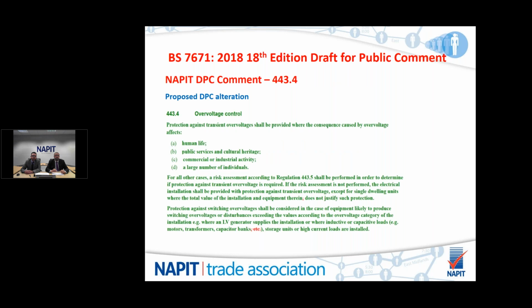Proposed DPC alteration, overvoltage control, 443.4. As an organisation, NAPIT are failing to understand how this can come in. It's asking for protection, surge protection, transient overvoltage, etc. But it's also saying that if it's a single dwelling unit and the total value of the installation, etc., doesn't justify any protection, you don't have to do it. Or it could be left for you to deduce whether you wanted to or not.